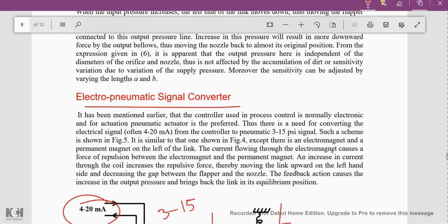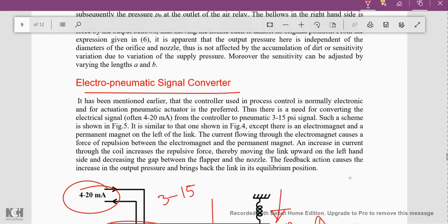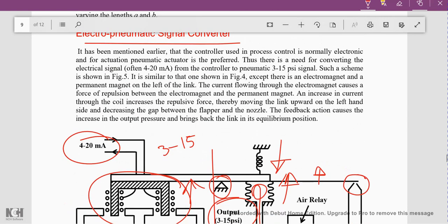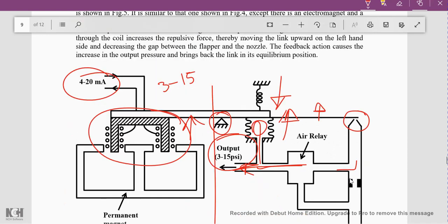This scheme is similar to the one shown earlier, except that here an electromagnet and a permanent magnet are used on the left-hand side of the link, whereas before only a mechanical bellow was used. The current flowing through the electromagnet causes a repulsive force between the electromagnet and the permanent magnet. Increase in current increases the repulsive force, moving the link upward on the left-hand side, decreasing the gap between the flapper and nozzle. The feedback action causes the output pressure to increase and brings the link back to its equilibrium position.